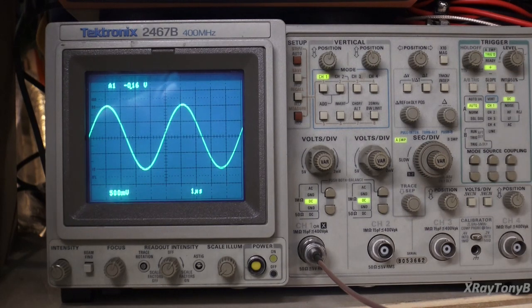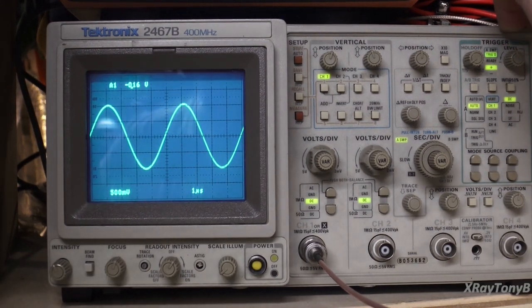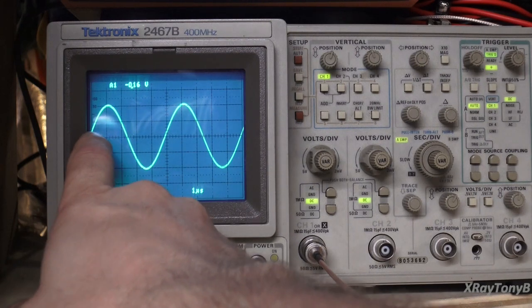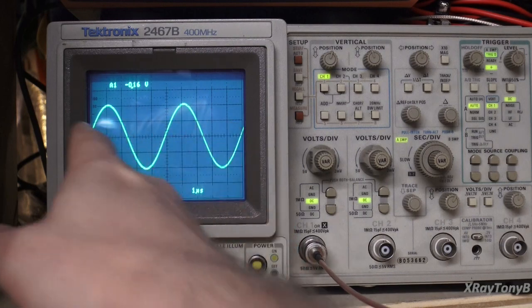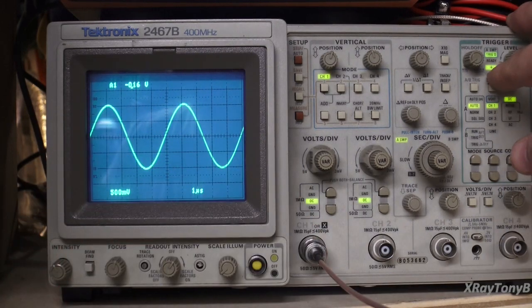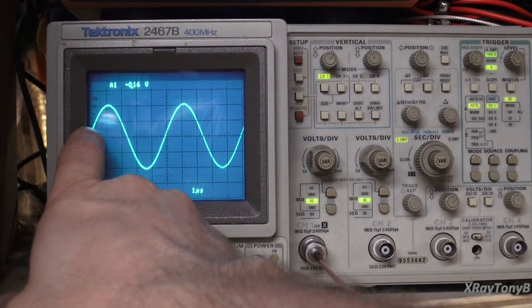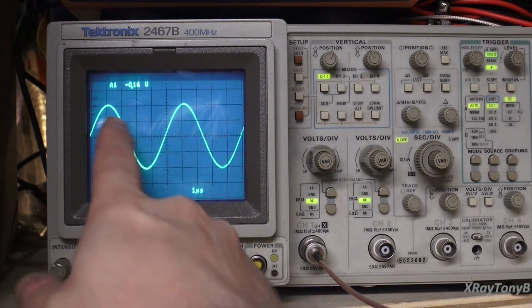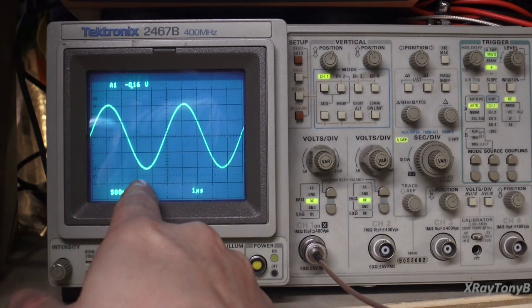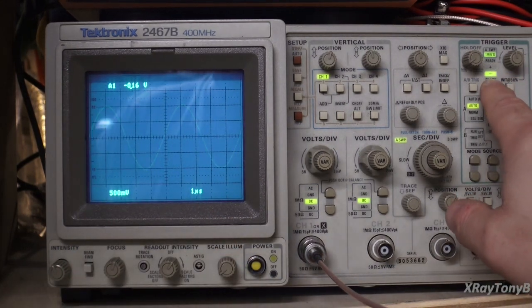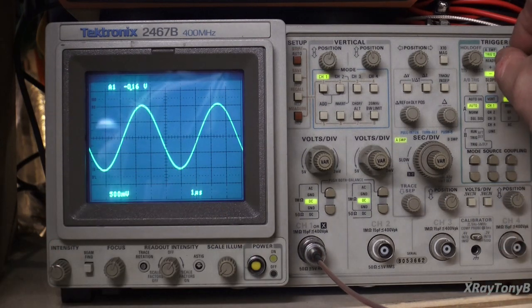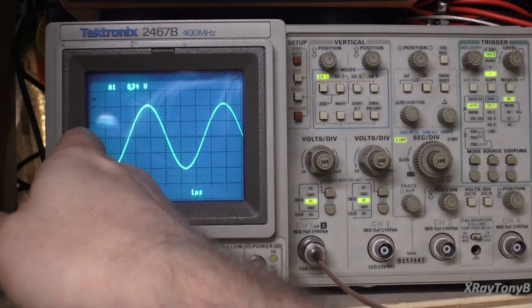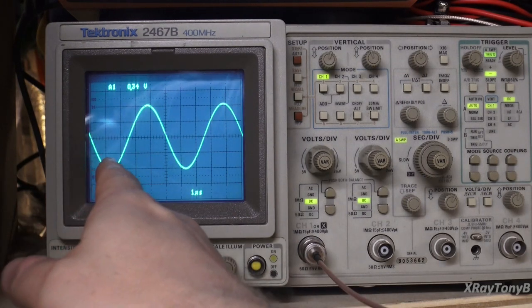Now, what does that mean? The slope means not only do I have to have that level, I have to have, let me back up. I'm confusing everybody and confusing myself. The level is how much change has to happen from 0 volts before you start to trigger a sweep of that dot going from here to here. The plus and minus tells you which direction that amplitude has to change. So if I'm at plus, anytime it sees a rise in voltage, it's going to trigger. If there's a fall in voltage, in other words, the voltage is going negative, it's not going to trigger. If I change this to negative, that means trigger when you see a negative going slope. So right there, as soon as you see a negative going slope, the dot starts to move.